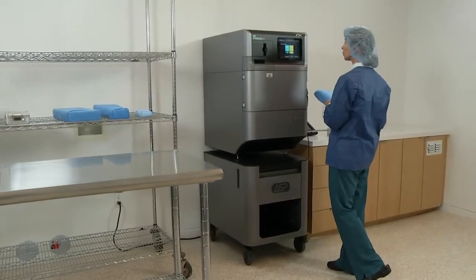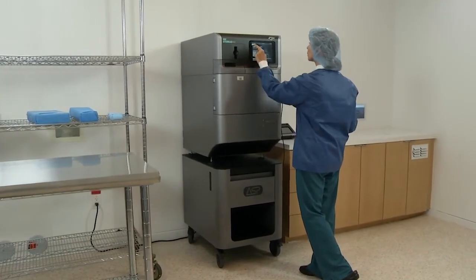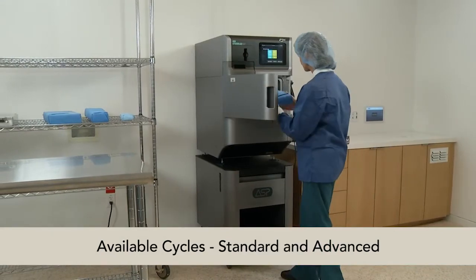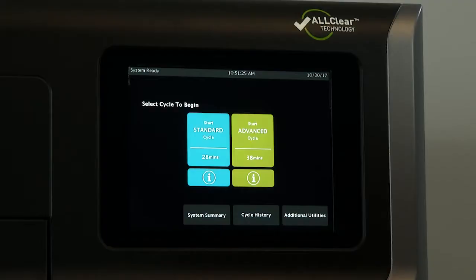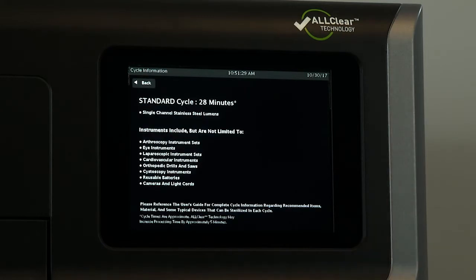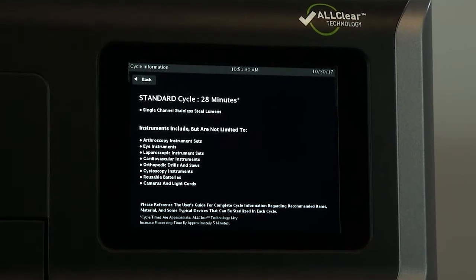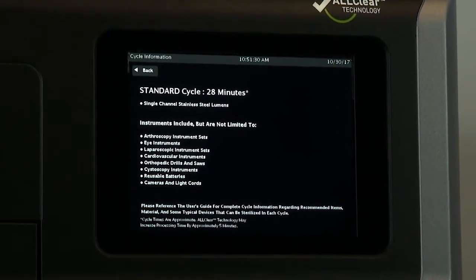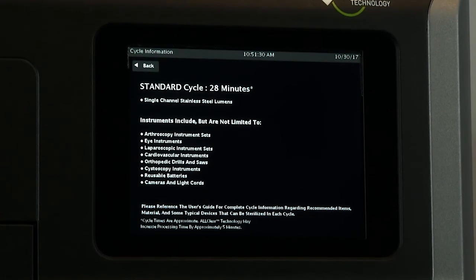Let's review the available cycles and what can be reprocessed in the STERAD NX sterilizer with ALLClear. The available cycles are standard and advanced. The standard cycle is 28 minutes and should be selected for single-channel stainless steel lumens with an inside diameter of 1 mm or larger and a length of 150 mm or shorter, and single-channel stainless steel lumens with an inside diameter of 2 mm or larger and a length of 400 mm or shorter. Typical devices would include arthroscopy instrument sets, eye instruments, laparoscopic instrument sets, cardiovascular instruments, orthopedic drills and saws, cystoscopy instruments, reusable batteries, cameras, and light cords.